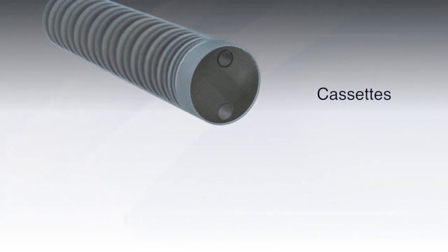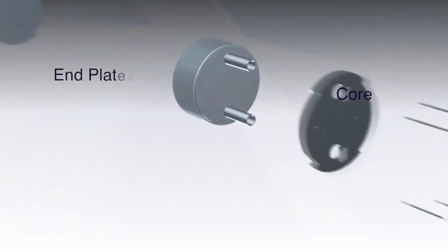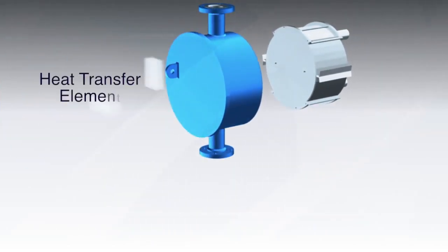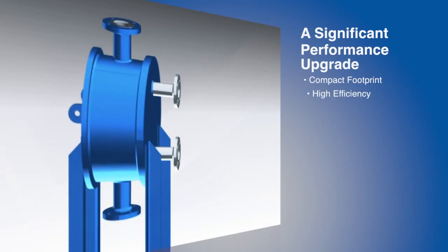Here's the inside story. The heart is its heat transfer element, composed of plate pairs welded into cassettes. Cassettes are perimeter welded to each other to form a core. A patented cage structure, welded only to the shell cover, surrounds and supports the core. Metal shell side flow directors, nozzles, and an end plate are welded to the core.